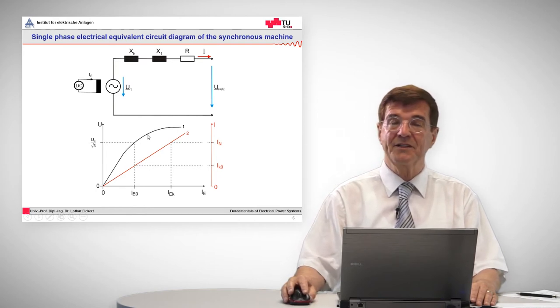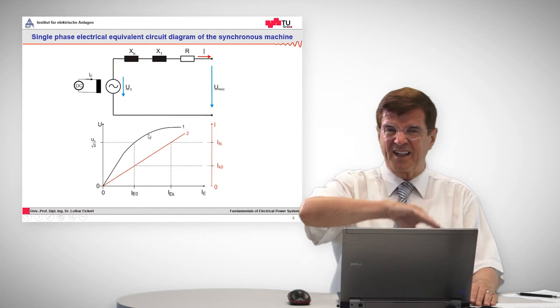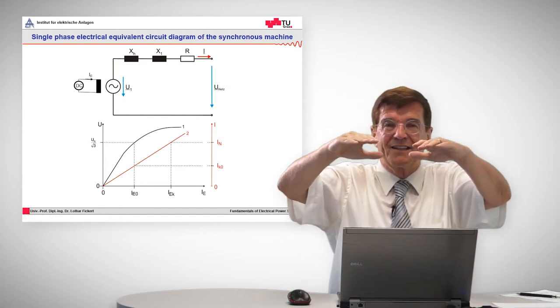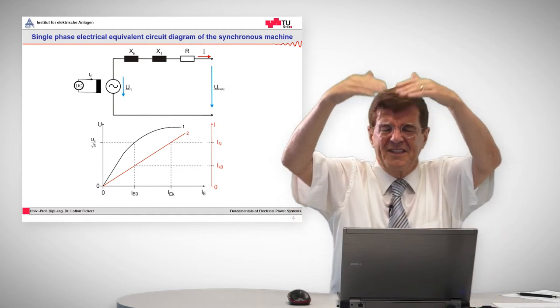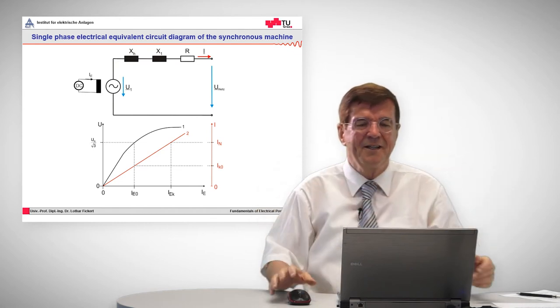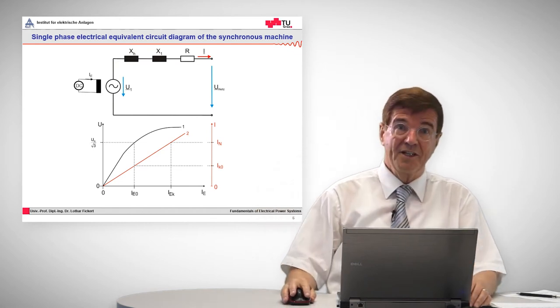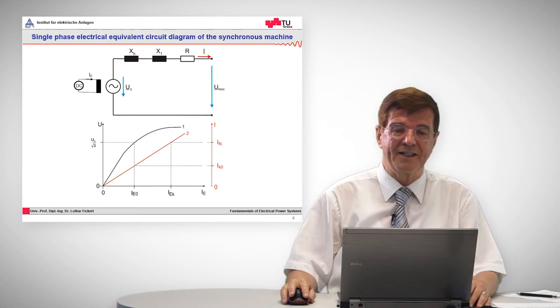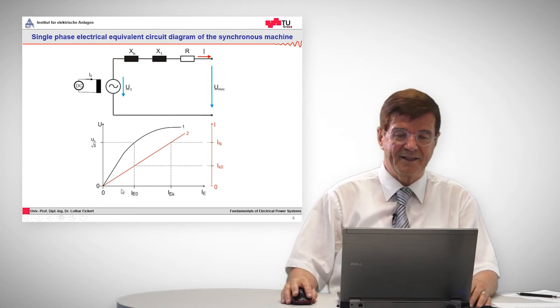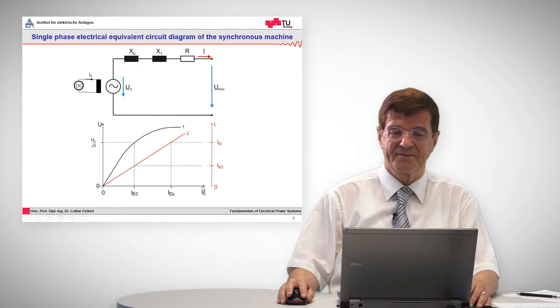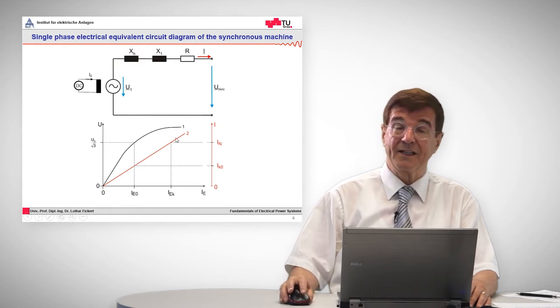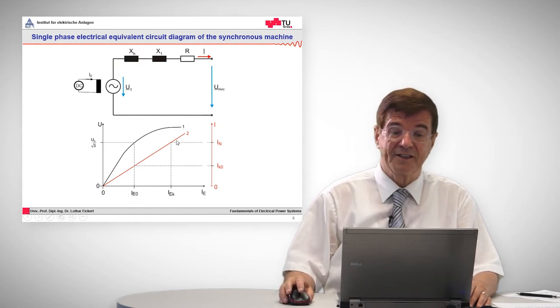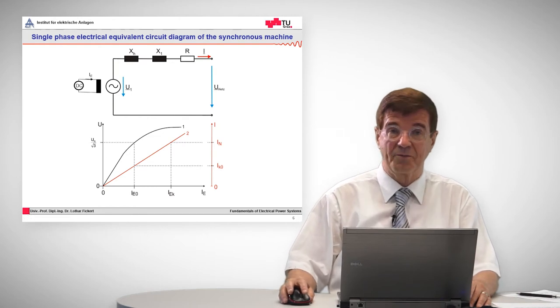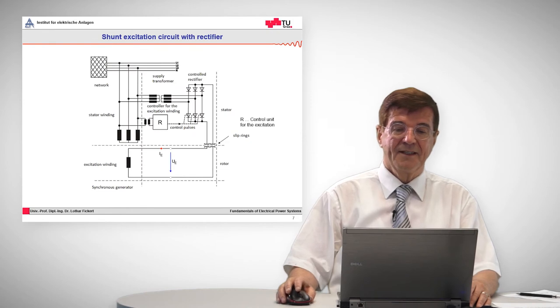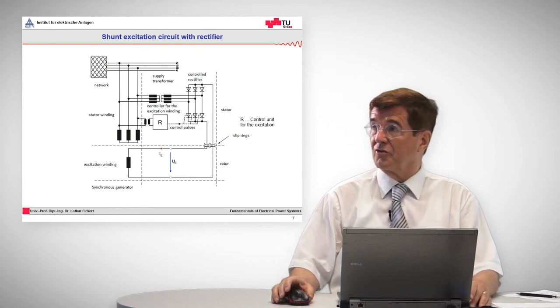But because of the material properties of the iron, there is something like a saturation, so the induction does not increase anymore, but is more or less becoming stable, and that means that the output voltage does not increase at the same rate as the exciter current does. In contrast, this red line shows the short circuit current. The short circuit current is strictly proportional to the exciter current. Just a view into technology.